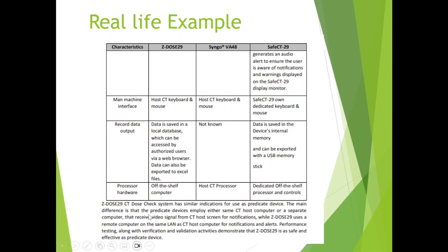However, there are some differences, and our performance testing, along with verification and validation activities, demonstrate that our device is safe and effective. And yes, in the whole submission package, you need to provide detailed performance testing and those verification and validation tests to support your claims.